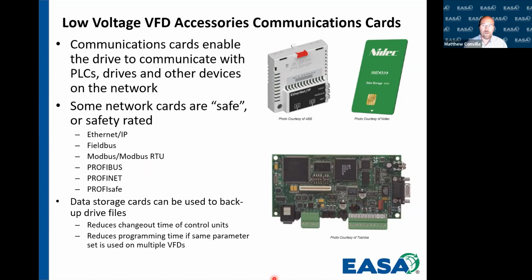So as our drive systems have gotten more intelligent and our applications are getting more intelligent, we're really wanting to protect the people that are in those areas. And we have safety ratings associated with that. So these drives now are more intelligent than that as well. So they have what we call STO, or safe torque off functionality. They have safety e-stop functionality, and they even have safety from a communication perspective so that the communication card is safe, like what we see here with the ProfiSafe.